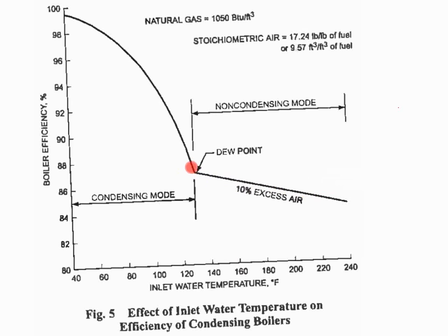And I get to save that energy instead of letting that energy go up the stack. Those flue gases are going to condense somewhere. They can either condense outside when they hit the cold air, or they can condense inside my heat exchanger, and I save that heat. I want to condense them inside the heat exchanger, right? So then my efficiency spikes up very dramatically. And if I give it really cool water, like 80-degree return water, all of a sudden my 86% boiler is a 96% boiler. It's a pretty dramatic difference.